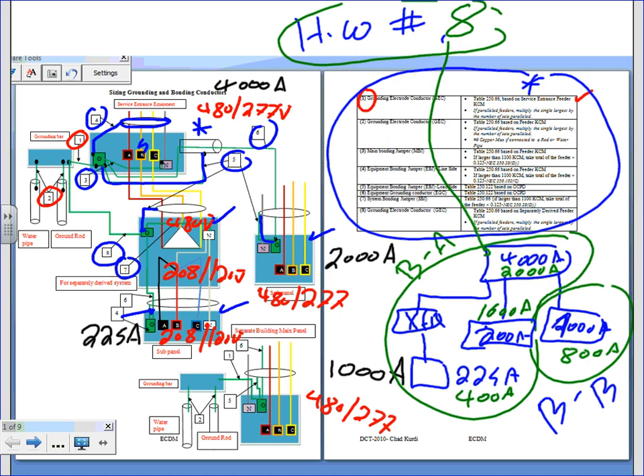Now, here's my question for you guys. If that switchgear was 600 and everything is 600 and this one continued to be 480/277, would the calculation be different? If everything is 600 volt, but this transformer is taking 600 to 480/277, would the calculation be different? No. Up to 600 volt, guys, what you did is basically the same. Doesn't matter what the voltage is. The way we calculate doesn't matter, because the answers will be different, since based on the voltage we find a few things. But up to 600 volt, this calculation is valid. DC is slightly different. High voltage is slightly different. Not that by much, by the way.